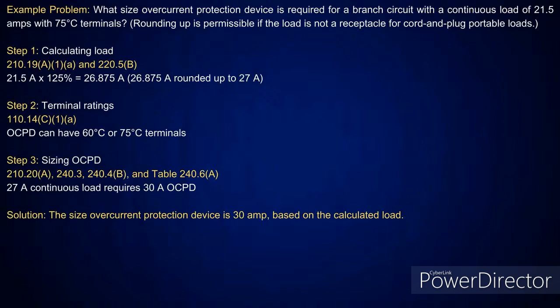You can leave it there, just round it up to 27 amps. Now, as I look at sizing the overcurrent protection device, you're going to see the same in 210.20(A), and it's going to tell you that you've got a continuous load. Then I look at Table 240.6(A). The next size above that is a 30 amp overcurrent device based on the calculated load.